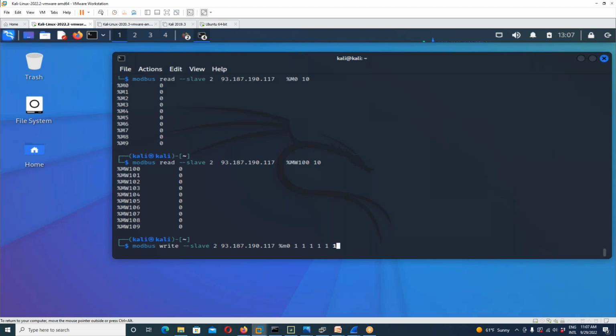Now remember that in Modbus, you have to put in values contiguously. It doesn't have the ability to go to a memory area and specify a particular memory area. You've got to start at a starting memory space and then fill in the values of each contiguous value there. It's pretty simple and lightweight.